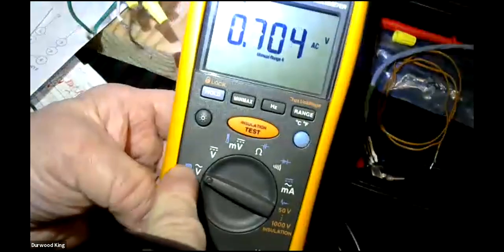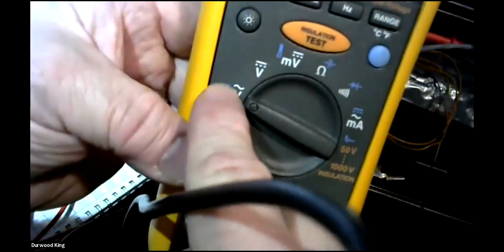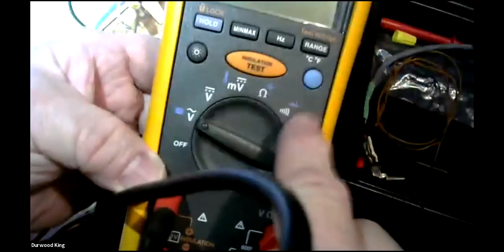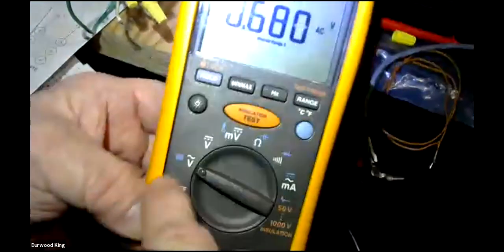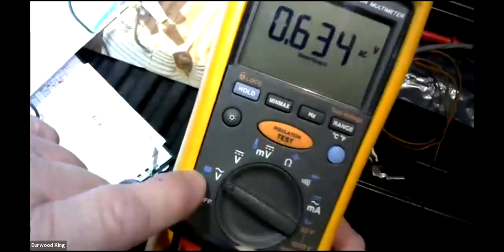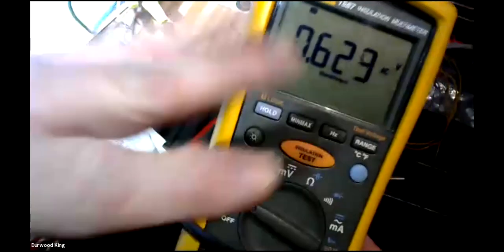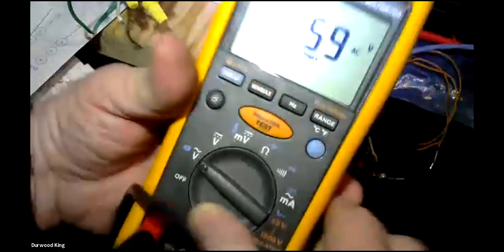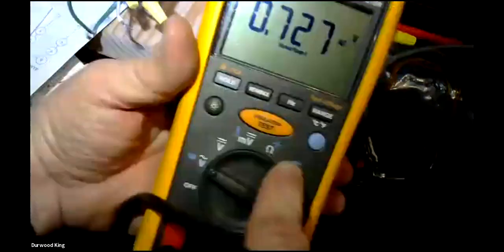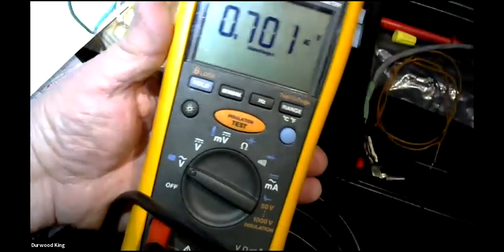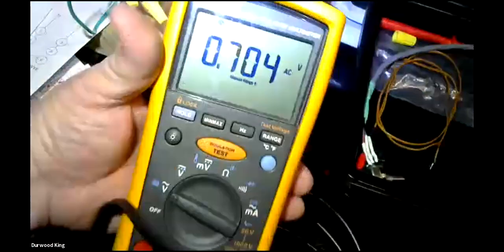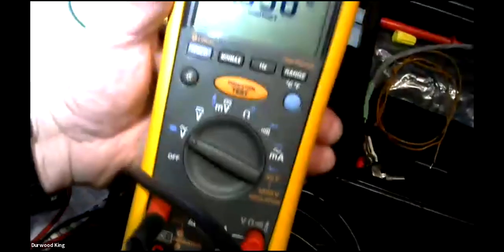If you have a VFD output, you put it on AC volts and hit the blue button. It filters out harmonics that can confuse a meter. This is a true RMS meter that can read the output of a VFD very accurately. I'll show you Thursday night how this works with a VFD, checking the output to the motor, and also a handheld digital scope that draws the waveforms, so you can see what the waveform looks like leaving the VFD at different frequencies. So try hard to be here Thursday, okay?